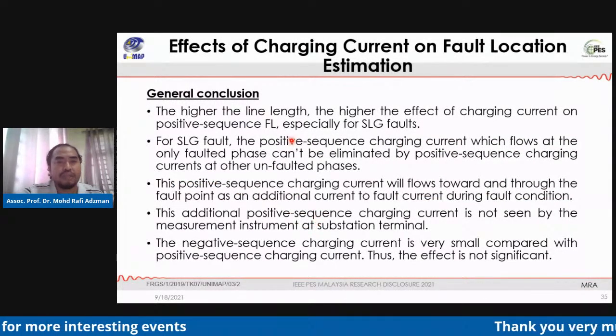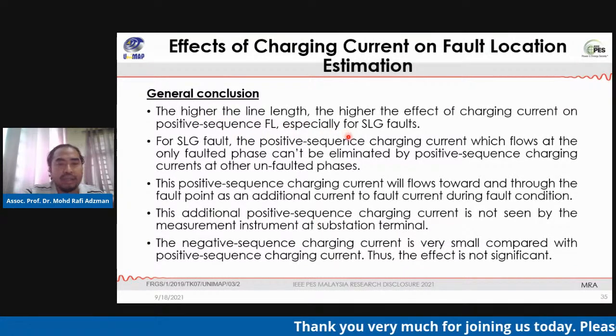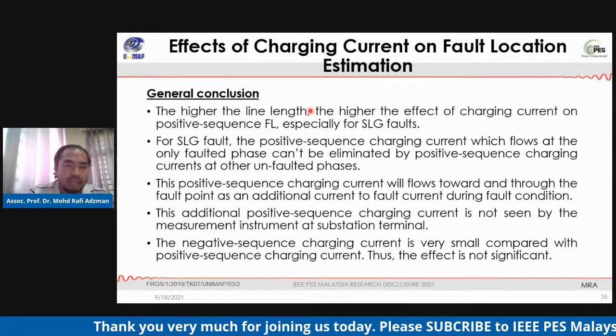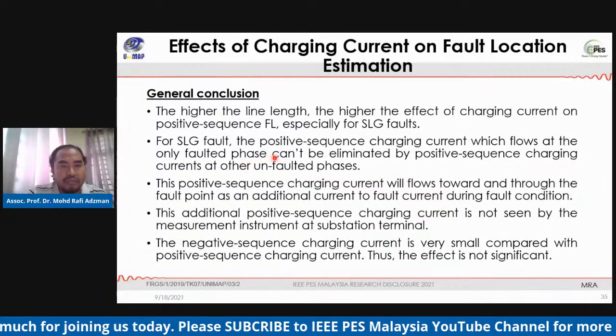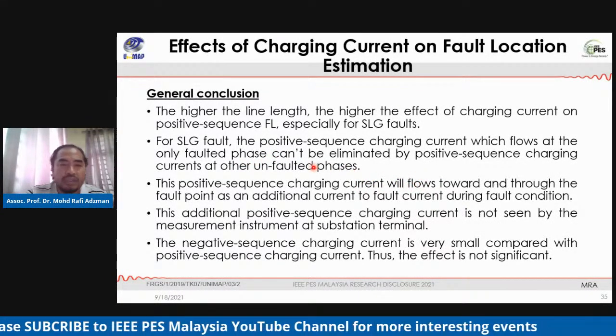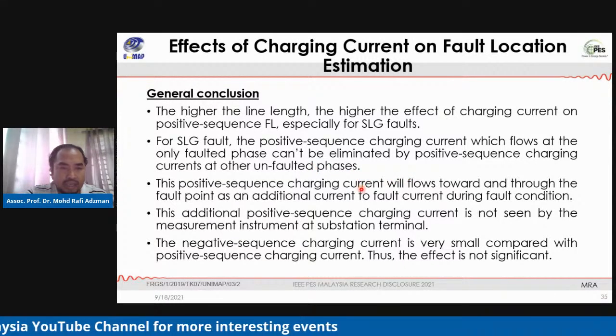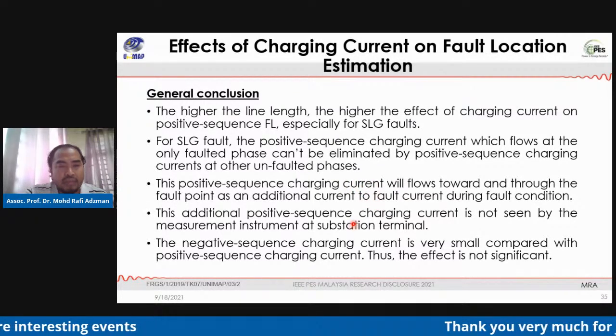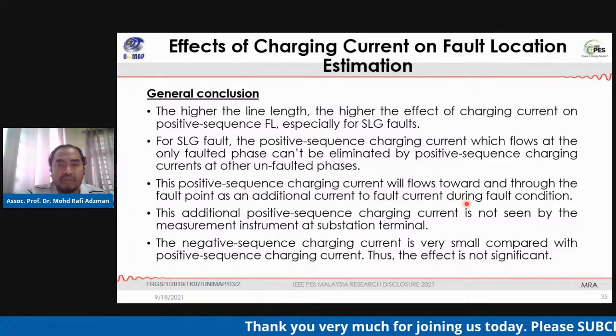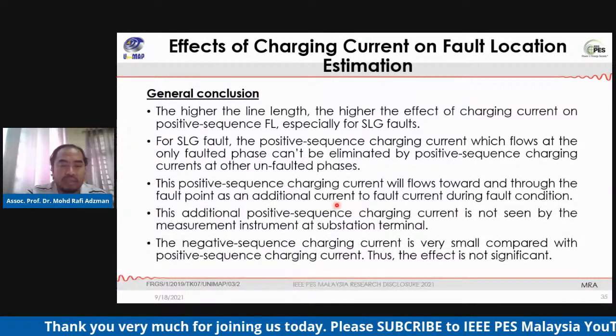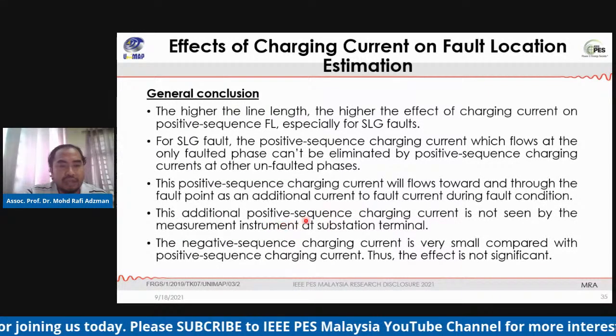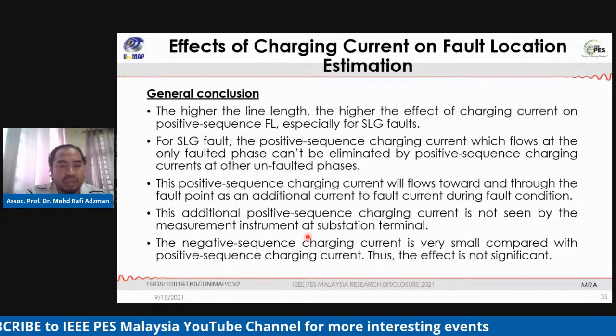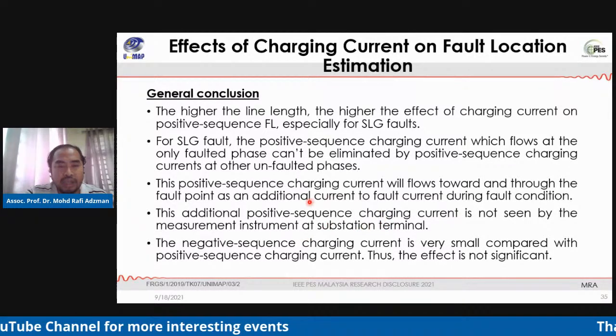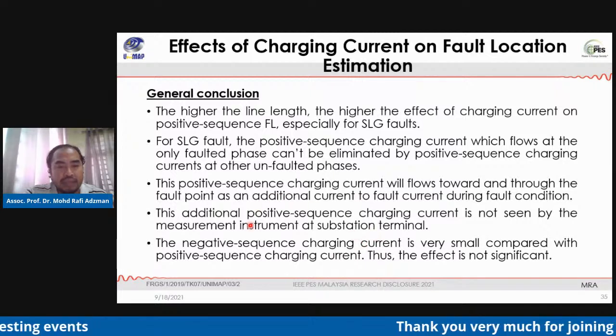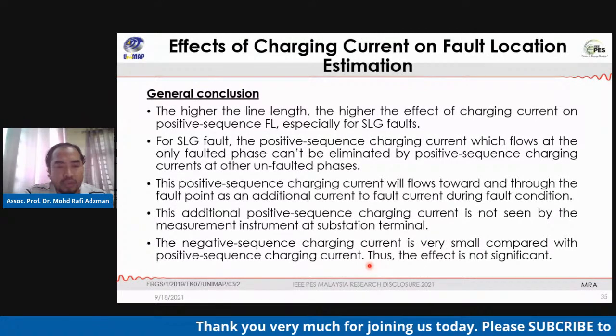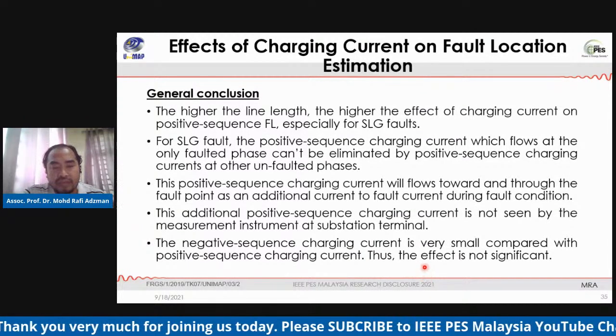Okay, general conclusion due to the effect of the charging currents. The higher the line length, the higher the effect of charging current on the positive sequence fault location, especially for single line to ground faults. For the single line to ground fault, the positive sequence charging current which flows at only the faulted phase cannot be eliminated by positive sequence charging currents in the other unfaulted phases. You can see that the positive sequence charging current will flow through the fault point as additional current to the fault current during the fault conditions. This additional positive sequence charging current is not seen by the measurement instrument at the substation terminal. That's why it affects the fault location algorithms. While the negative sequence charging current is very small compared with the positive sequence charging current. Thus, it does not affect the fault location algorithms.